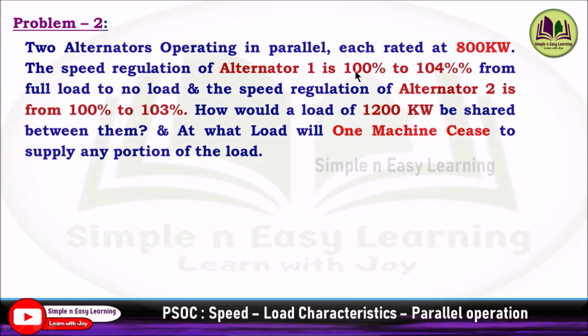Alternator 1 is 100% to 104% from full load to no load. Usually problems mention from no load to full load there is a drooping characteristic, but here the problem gives from full load to no load the speed regulation is 100% to 104%. That means 4% droop for alternator 1 and similarly for alternator 2 there is a 3% droop. First we need to find how the alternators share the load of 1200 kilowatt, and if one machine ceases to supply any portion of the load, what additional load is supplied by the other machine.